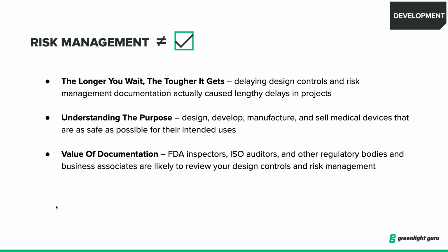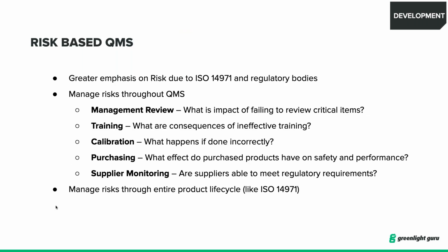Risk-based QMS, I told you I'd talk a little bit about that. Let me share a few concepts of that. I think the part that gets confusing to people is that they're reading 14971 and they're like, that's about product risk management, and 13485 says thou shalt have a risk-based approach, refer to 14971. What is that all about?